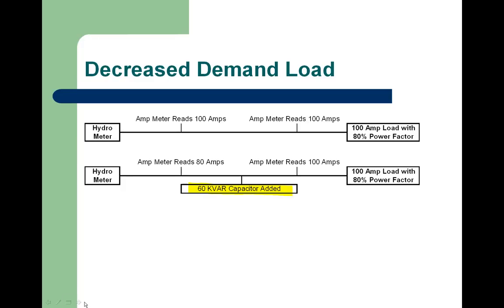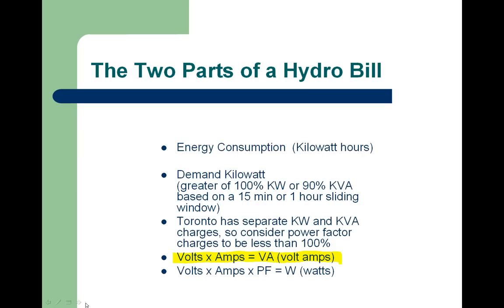The next slide shows the two parts of a hydro bill: the energy, which is kilowatt hours, and the kilowatt demand. Now, we're talking about Ontario here, so in all areas other than Toronto, the kilowatt demand that you pay in your hydro bill is based on 100% of kilowatts or 90% of kVA, whichever is greater. And this is typically a demand on either a 15-minute or a 1-hour sliding window.